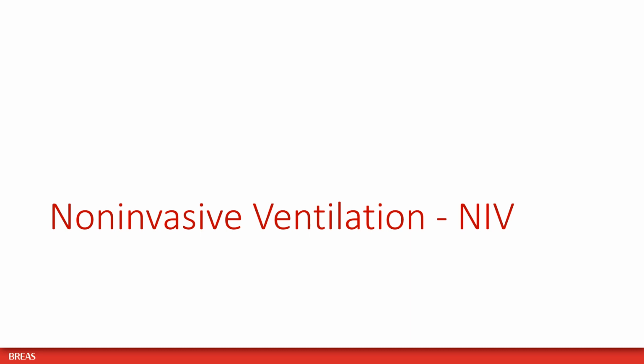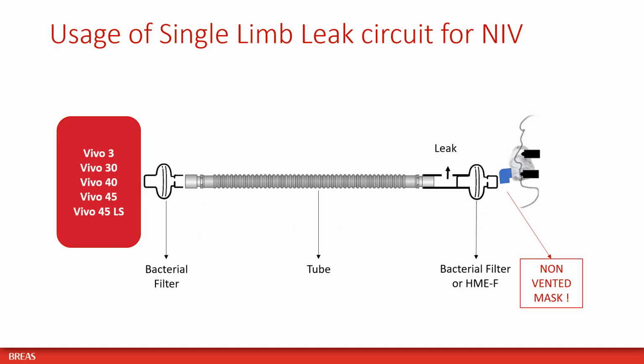Please adhere to the following recommendations when using your Vivo ventilator for non-invasive ventilation. When using a single limb leak circuit for non-invasive ventilation, please select a non-vented mask as patient interface and place a bacterial filter at the air outlet of the ventilator, as well as a bacterial filter or HME with filter in between the leak adapter and the patient mask.